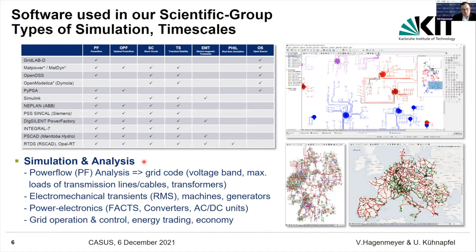What can we do with simulation analysis using these digital twins? We can do power flow analysis to check grid code — whether voltage bands are respected, lines are not overloaded, and transformers are capable of doing their job. We can study electromechanical transients to verify stability, including machines, generators, power electronics, and new devices — modeling them first on the virtual side and then deploying in real life. This covers all aspects of grid operation, control, economy, and energy trading.